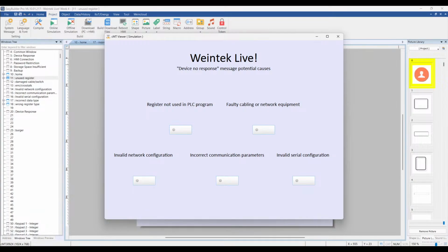If the DNR message is IP address or cable related, you can most likely tell because often no data will be transferred and no objects within your project will display. So like we saw earlier, one of our objects was missing because it had a tag assigned to it that was no longer within our PLC project.